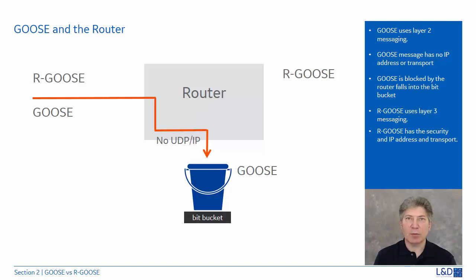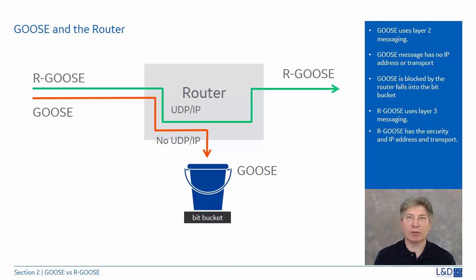The R-GOOSE is a multicast layer 3 messaging service designed for use in a wide area network environment. It has UDP and IP headers assigned to it, which allows the R-GOOSE message to pass through the router's firewall.